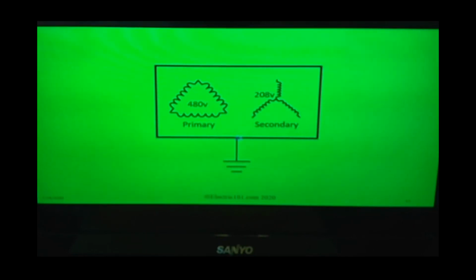Now, the requirement here is the transformer case has got to be connected to earth. Well, this transformer is going to create magnetic fields, and as these magnetic fields expand, that's going to induce a voltage right there on that casing. So that transformer winding case has got to be connected to ground. So every case is connected to ground, regardless of whether it's a grounded or ungrounded system. But standard voltages don't exist.